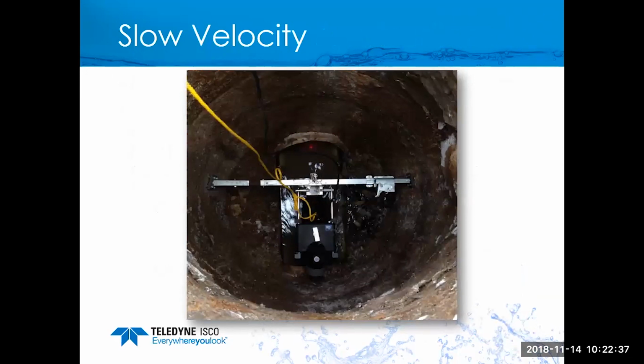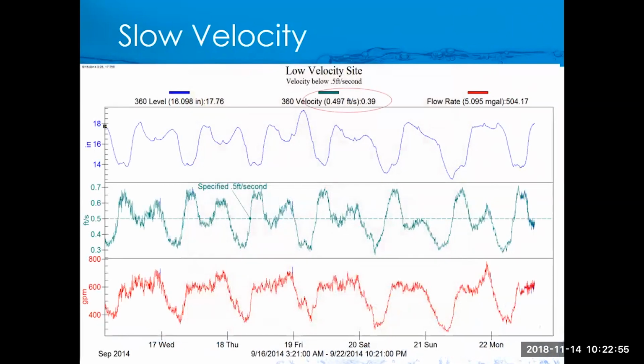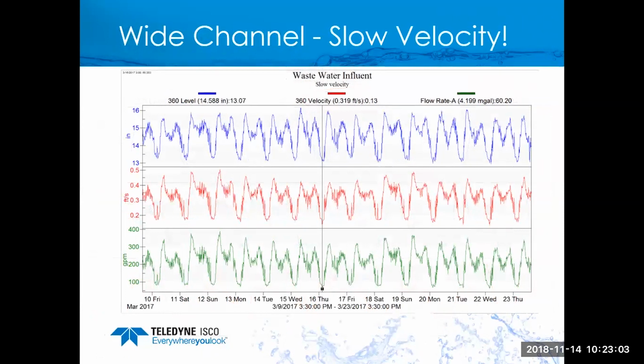So here's a good picture of one. You can see the laser dot on the water. And this is a temporary mount. So the laser gets its level reading, then focuses the laser into the flow. That water is almost like glass. And so with the laser, we don't care what the surface is doing. We're looking below the surface. Here at this location, you can see the dashed line in the second pane is half foot per second. In this case, our point was 0.39 feet per second, so very, very slow.